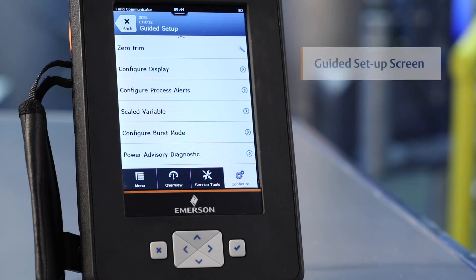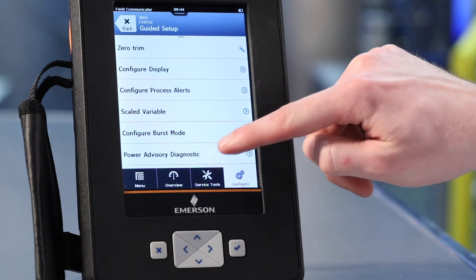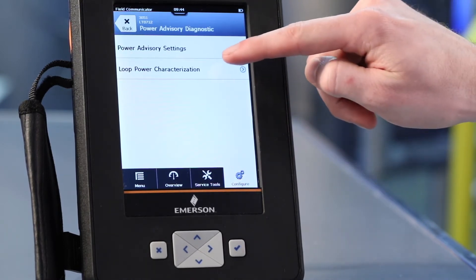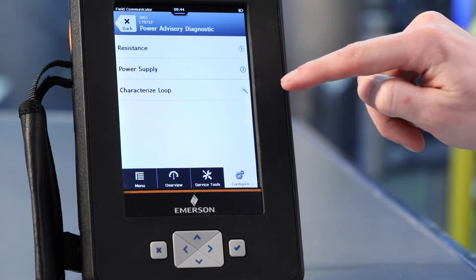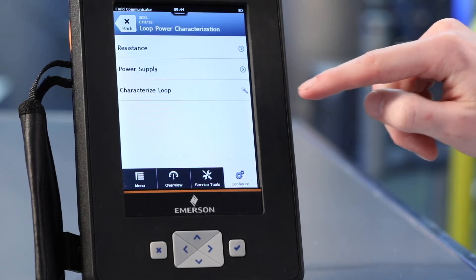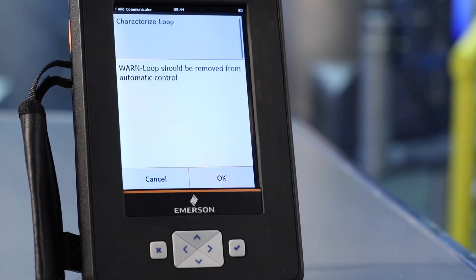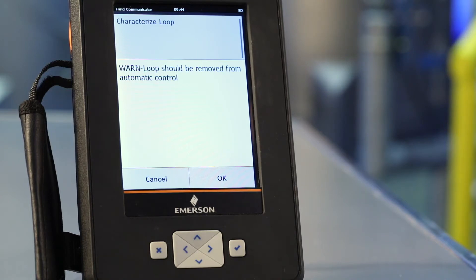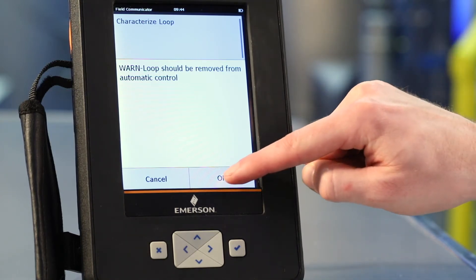Once connected, navigate to the Guided Setup screen. Select Power Advisory Diagnostic, then select Loop Power Characterization, then click Characterize Loop. This characterization will baseline the electrical loop so the transmitter sees what proper operation looks like. The next screen is a warning that the transmitter you are configuring will be removed from process control. Select OK.